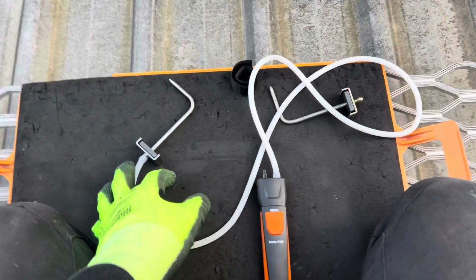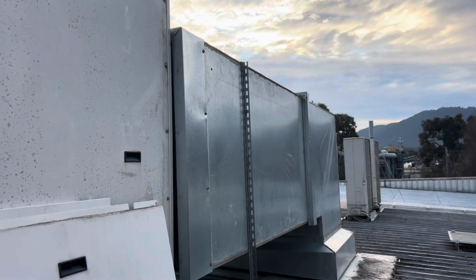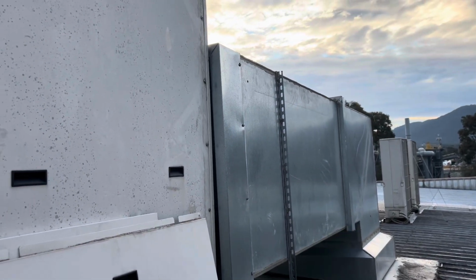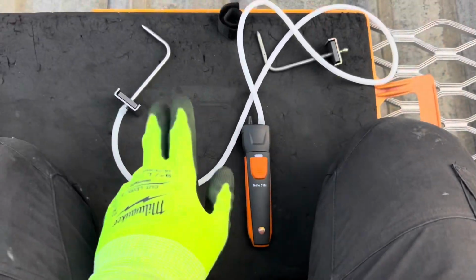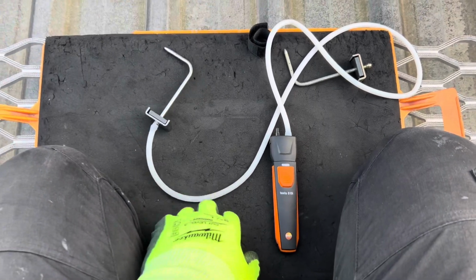Just went through and did a quick static pressure measurement. I drilled holes the other day, but it was more for the probe, so I had to quickly do two measurements at one time. Anyway, it's sitting at about 110 pascals of static, so that's actually not too bad.